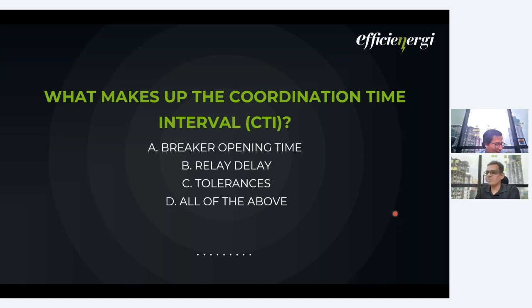Okay. So as expected, people have given the right answer. Almost 70% of the team has answered right. It is all of the above. So basically, as I explained, we only know the operating time of the relay. We don't have knowledge about the tolerances of the sensing equipment. We don't have the exact breaker opening time. Then we don't exactly have the same characteristics for the upstream relay. Downstream you might have a Siemens relay, but upstream you might have an ABB relay. So the characteristics of those two relays in terms of tolerances might be different, and we don't have that knowledge.